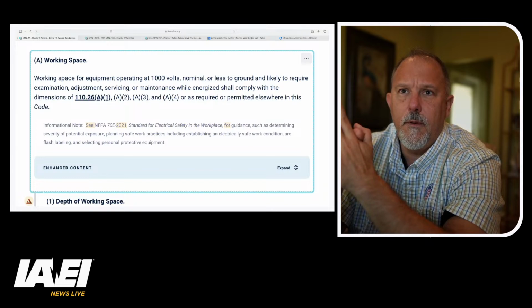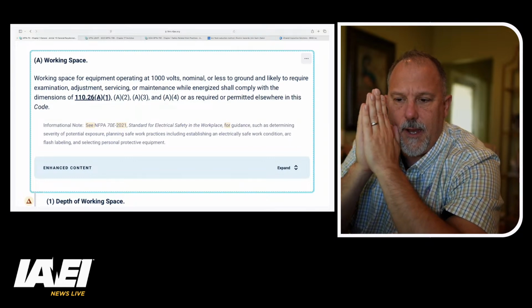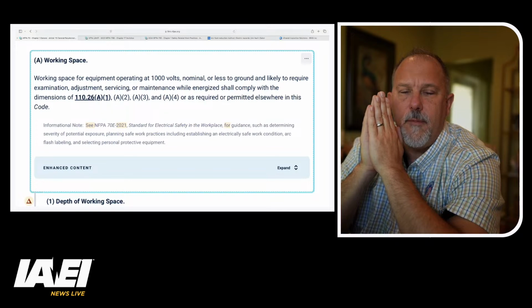So I would tend to agree. I'm leaning in the court now that for working space and other places where we use this phrase, likely to require examination, adjustment, servicing, or maintenance while energized. Maintenance, I may have to establish an electrically safe work condition beforehand, but I'm not going to be maintaining that disconnect switch while it's energized. I'm not going to be servicing it while it's energized. Servicing is a defined term in the National Electrical Code. I'm not going to be doing adjustments while it's energized, based on 70B. And I will not be examining it. The only thing I am doing is verifying absence of voltage, and I would argue that is none of those.